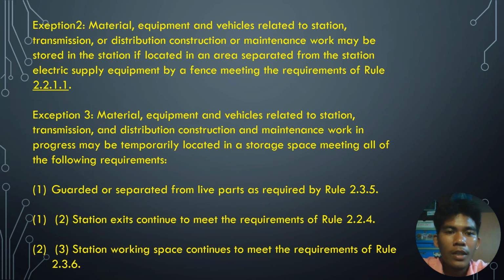Exception number 2: material, equipment, and vehicles related to station, transmission, or distribution construction or maintenance work may be stored in the station if located in an area separated from the station electric supply equipment by a fence meeting the requirements of Rule 2.2.1.1. Exception number 3: material, equipment, and vehicles related to station, transmission, and distribution construction and maintenance work in progress may be temporarily located in a storage space meeting all of the following requirements. They are guarded or separated from live parts as required by Rule 2.3.5, and the station exits continue to meet the requirements of Rule 2.2.4.